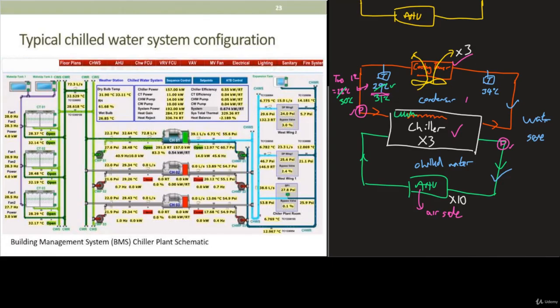Of course, it's impossible to put all the AHU readings, all the temperature of your air into one single page. So usually BMS has multiple pages, usually differentiated into different AHU. For example, AHU 1-1, you will see all the temperature readings, all the parameters inside AHU 1-1. Then you may have AHU 1-2, 2-1, etc. So that's how this system is being set up at the FCC, and a person can just sit there and monitor the whole chilled water system configuration from a single location.